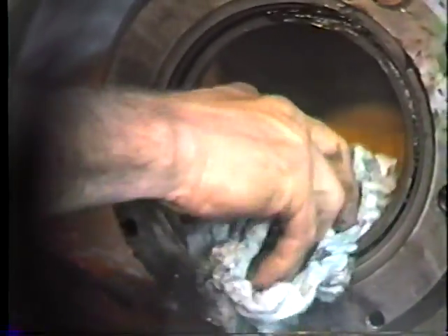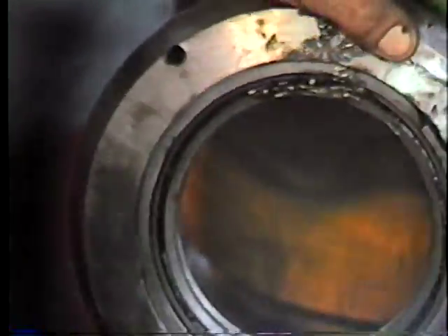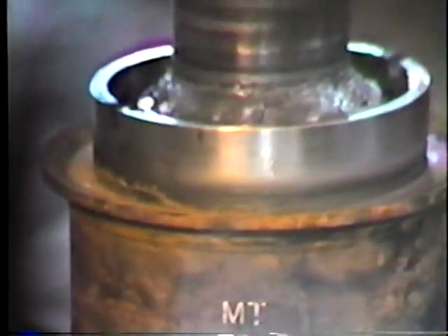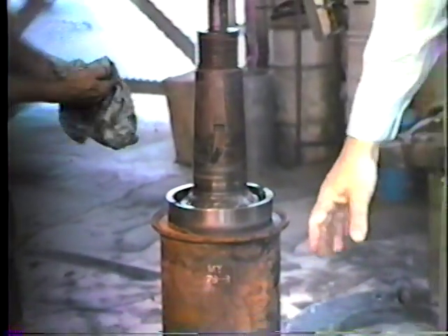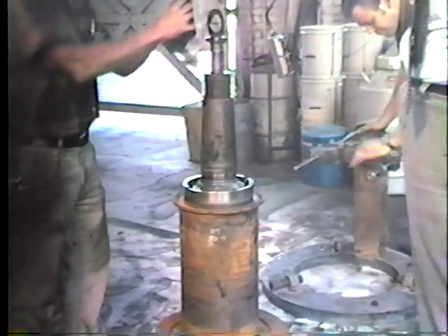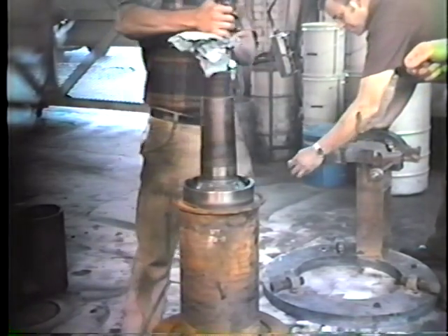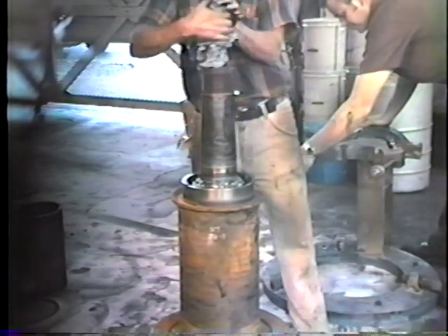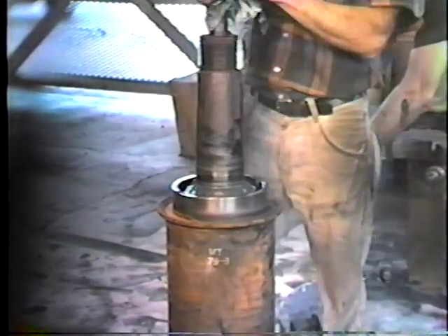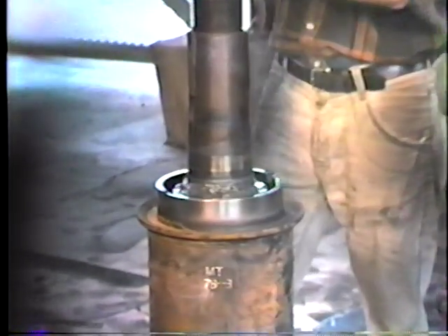Was this journal movable when you received it? Right. Okay, put that down. Rotate the journal for me. Can you twist that by hand? The O-ring also is in good shape on the seal carrier. All right, can you rotate the journal by hand? It rotates very easily. So there's some question as to why this journal was sent back. Right. This is a close-up of the seal area there.